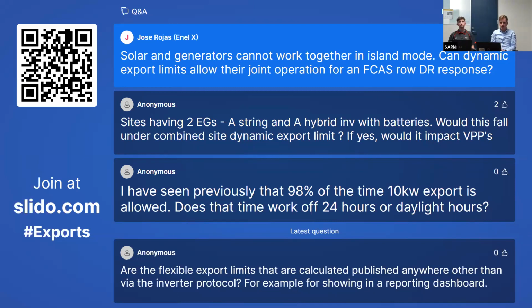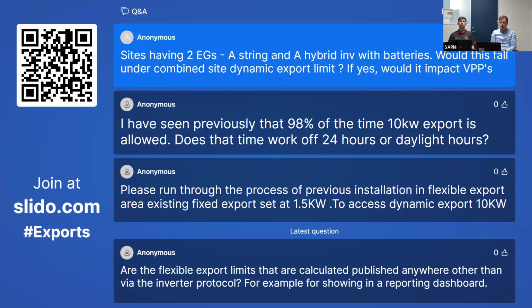Thank you. Sites having two EGs, a string and a hybrid inverter with batteries, would this fall under combined site dynamic export limit? If yes, would it impact VPPs? Yeah, so if we've got two generators on site, basically, yes, it's a site-wide export limit. So at the moment, there'd need to be controls in place to make sure it doesn't exceed the static limit. Under a dynamic export arrangement or a flexible export connection agreement, there'd need to be controls that would ensure that the exports from those systems combined didn't breach the export limit for the site.